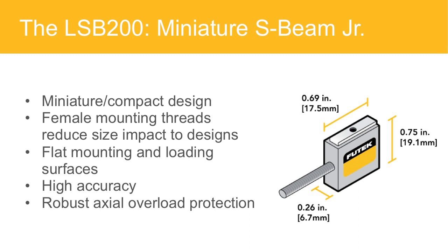becomes even more important. Just to explain the mechanism itself, if you look at the current slide, you'll see a female thread on the top of the load cell. We have a matching thread on the bottom, which you cannot see in this image. You attach to those female threads, applying a tension or compression load accordingly to provide stimulation to the load cell.